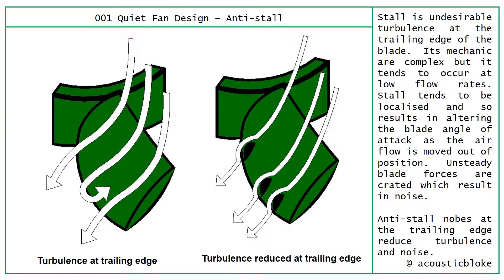Moving to air as it passes off the trailing edge of a fan blade, we can get something called stall — an undesirable turbulence at the trailing edge. It tends to occur at low flow rates, is localized, and results in altering the blade angle of attack so airflow moves out of position, creating unsteady blade forces and noise. Anti-stall knobs, visible in black on the right-hand image, help to even the flow over the trailing edge, reducing turbulence and thereby reducing noise.